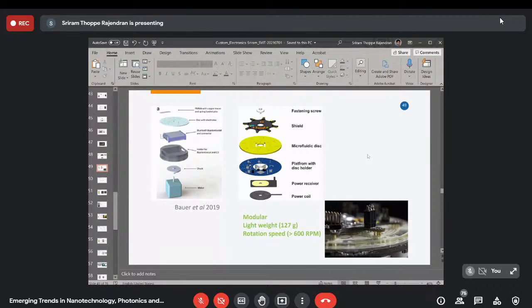But I can still tell you the problem with their platform is that the connection to the electrode is still a problem. Since it is still a heavy device, it has certain momentum. If they want to start and stop spinning in centrifugal microfluidics, you need to control it very precisely. Because of the weight, the control of speed was very much hampered. The other problem was that the connection to the electrode was very poor. As you spin, the contact points were moving due to the weight, which created a lot of noise during the measurement.